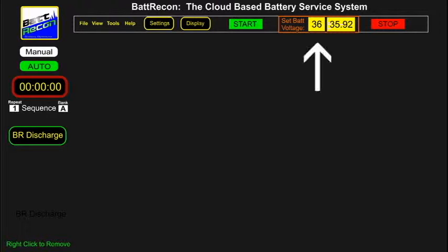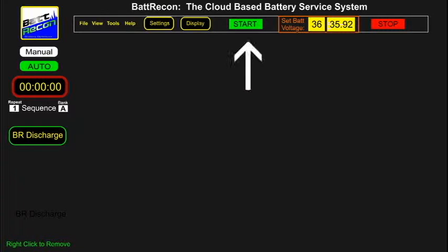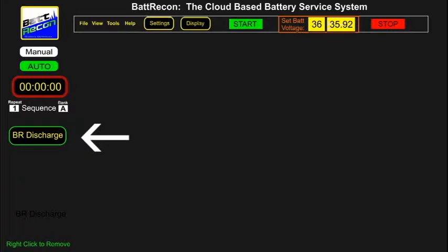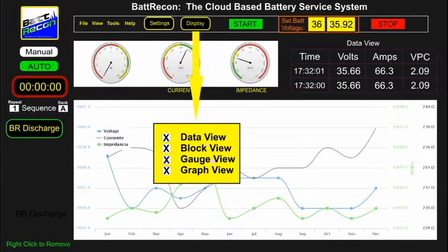When you're ready to start the device, select the battery voltage at the top of the test bar and change it to match your battery voltage. Then go to the top of the panel and left-click on the start button. The system will connect the battery to the BR discharge device, and the BR discharge device indicator will turn green when it is operating, and red when the BR discharge device is not connected. The device will remain connected until either the VPC threshold or the time threshold is reached, at which point the command and control system will disconnect the device from the battery.